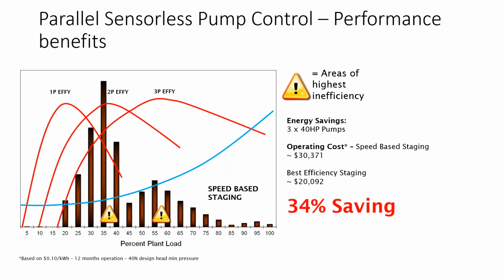So the performance benefits, you'll see here the speed staging. If you had 3 40 horsepower pumps involved here, your operating costs would be about $30,000 on speed-based staging. On best efficiency staging, you would have to be at around 20,000. So that's a 34% savings. That's substantial, and not to mention the carbon footprint, how many carbon dollars you're going to be wasting, tons of carbon.